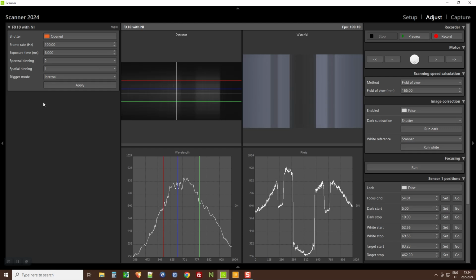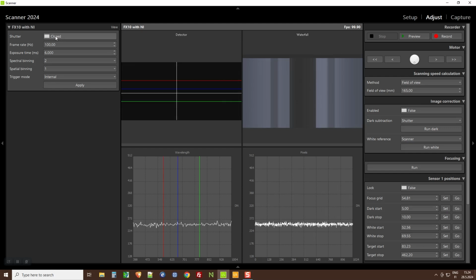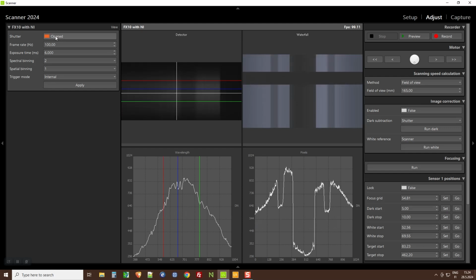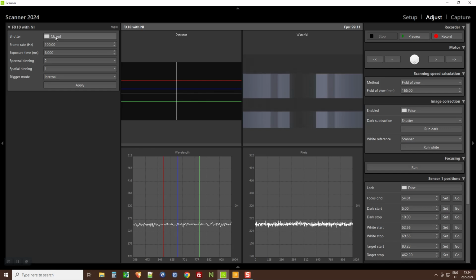On the left-hand side, we have all the parameters related to the camera, the acquisition parameters. All our cameras include shutters, all except the GX17, and here you can hear the shutter opening and closing. When it is closed, there is no light entering the camera, so you are recording the reading noise, the dark current, the dark noise, as you can also say, of the camera, because it's a sensor. Every sensor has noise.